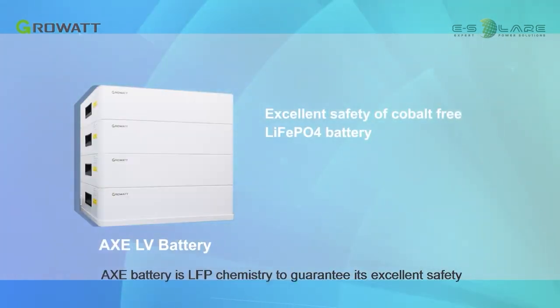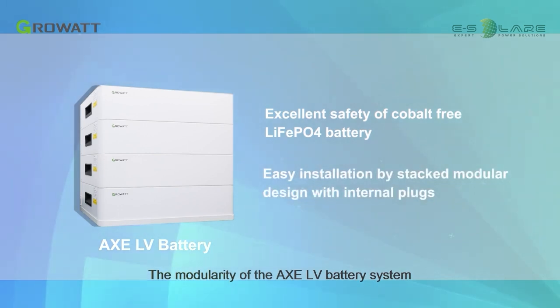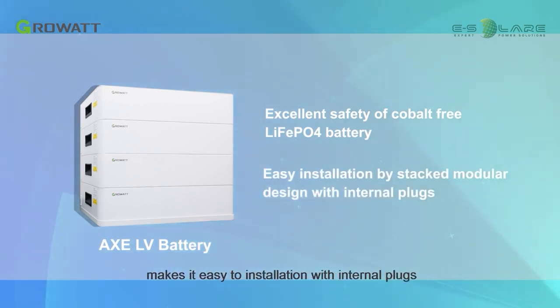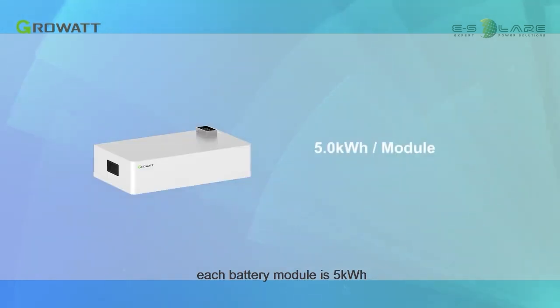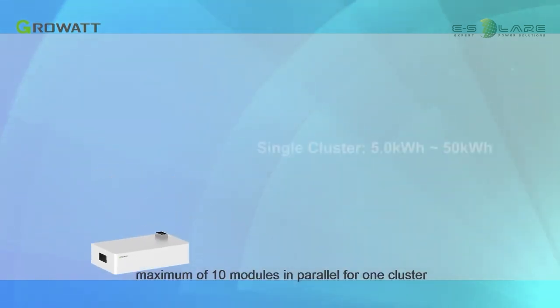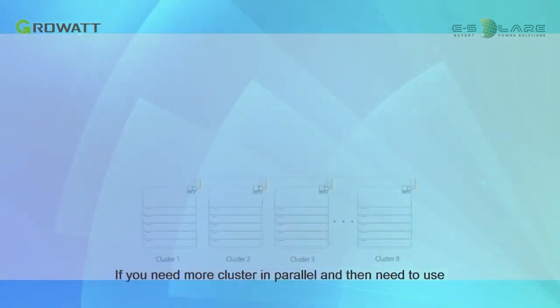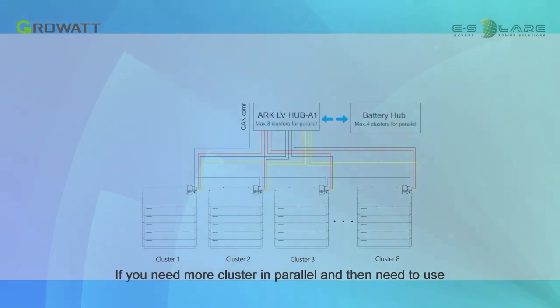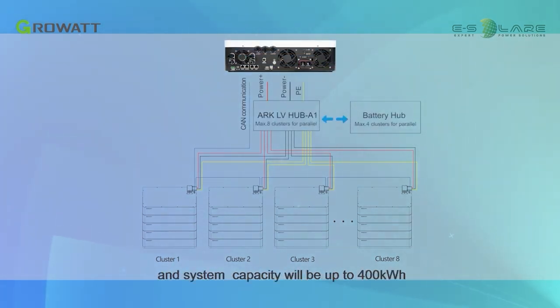The AXE battery uses LFP chemistry to guarantee excellent safety. The modularity of the AXE LV battery system makes it easy to install with internal plugs. Each battery module is 5 kWh, with a maximum of 10 modules in parallel for one cluster, so a single cluster capacity can reach 50 kWh. If you need more clusters in parallel, you can use the battery hub device, which can realize 8 clusters in parallel, and system capacity will be up to 400 kWh.